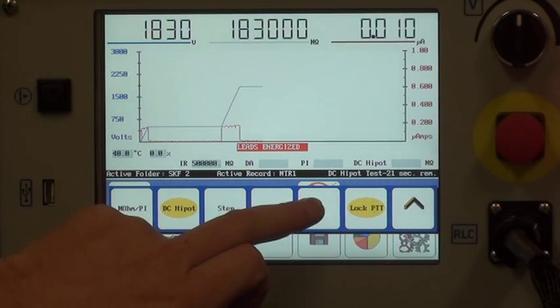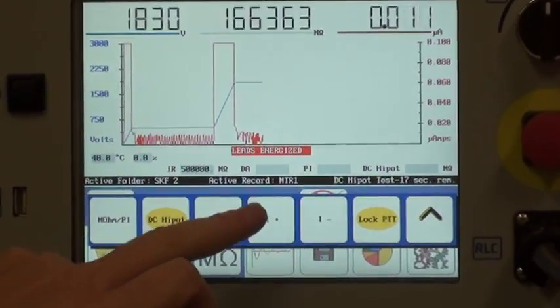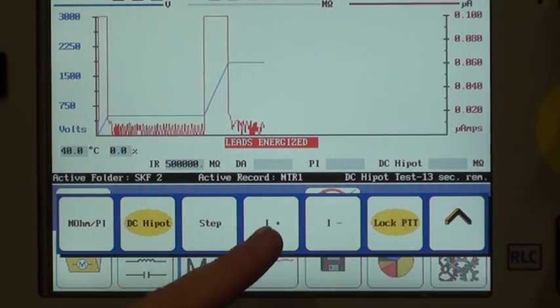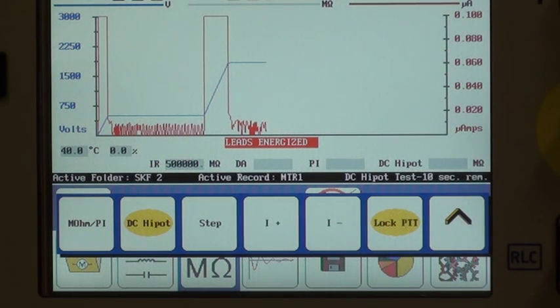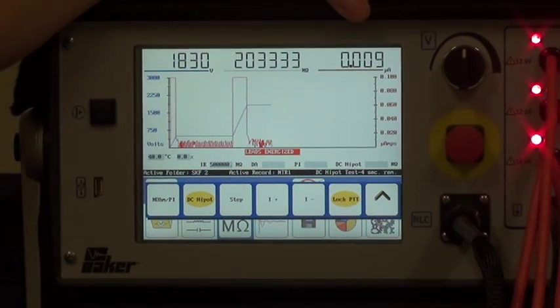Once again, the current leakage is adjustable, simply by activating the plus or the minus button on the screen here. As you can see, the megaohm value is very high but fluctuating, and the current leakage is very low.